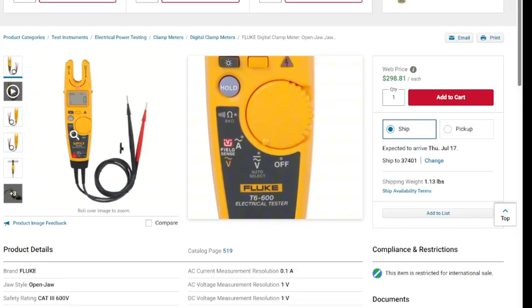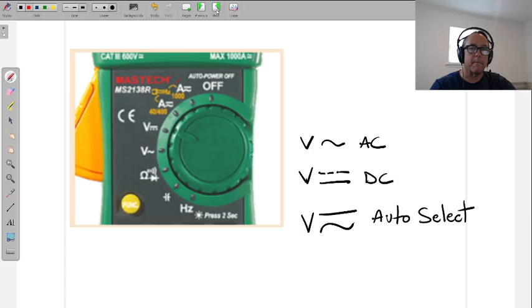This is why it's really good for troubleshooting in motor control settings, because motor control circuits often have different voltages throughout the circuit. I might be working on 480, 24 volt DC, going back and forth between AC and DC voltage, so I don't have to switch my meter, measure, switch again, measure. This is fine, but if you're doing this all the time, remember what I said yesterday about time, we're always trying to avoid steps.